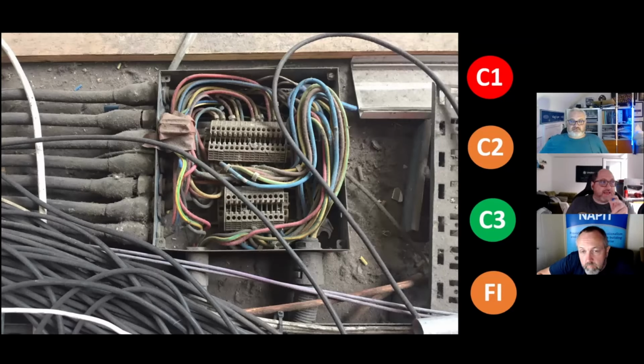I had the exact scenario in a factory, where I was up on a MEWP doing an EICR, and a lot of the old busbars in the mezzanine above were no longer in use but were still energized. So over time they'd started ripping out the fuses to recycle them for other parts of the factory, and they just left the boxes wide open with the mains still live.